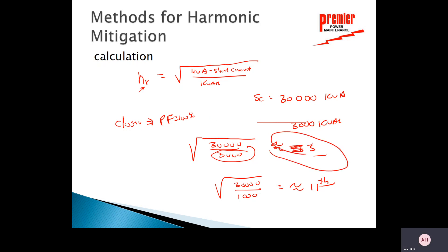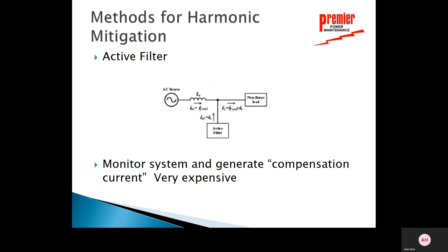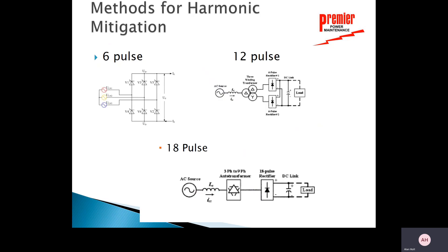Active filters are a newer, more expensive but very effective solution. The active filter monitors what is happening in the line and injects whatever frequency is required to cancel out the harmonics. It is relatively new and expensive, so most facilities cannot afford it.